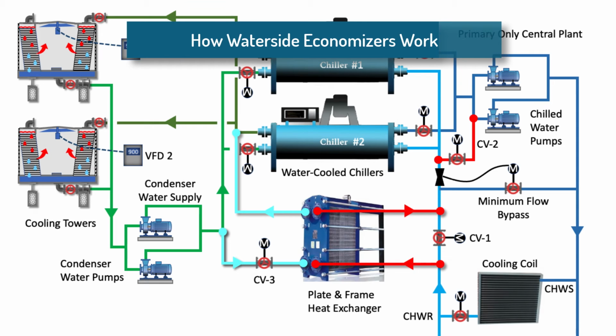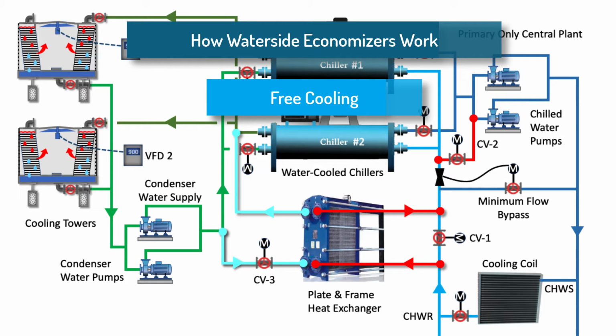In this video, we'll learn how waterside economizers work, also known as free cooling. We'll learn how to connect an economizer into a water-cooled and air-cooled chilled water system. 100% free cooling allows for the chiller to be shut off and the cooling tower along with a heat exchanger to do all the cooling. We will show you 3 waterside economizer configurations using a plate and frame heat exchanger.